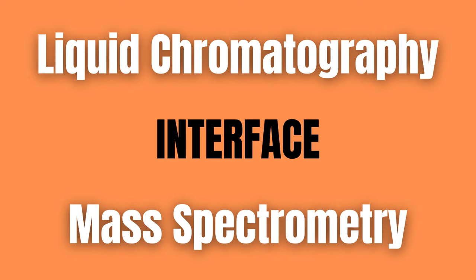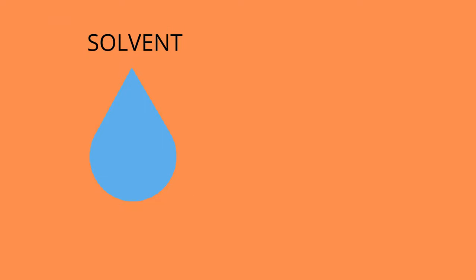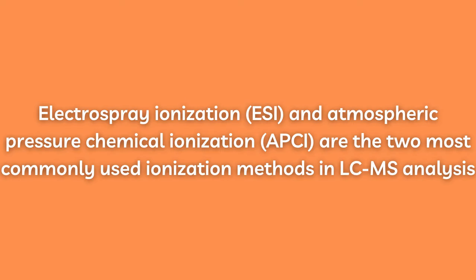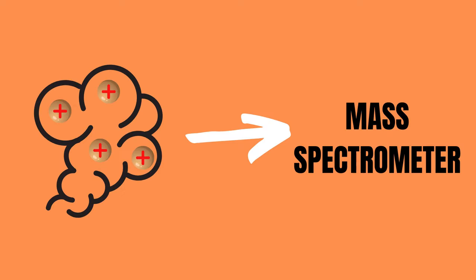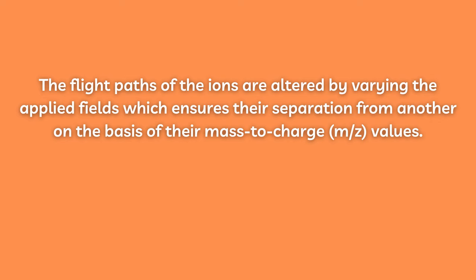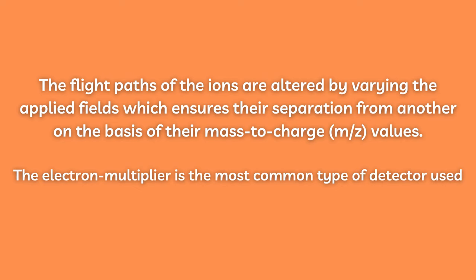The LC and the MS are coupled through an interface. The solvent is evaporated through the application of heat and analyte molecules are vaporized and ionized. This is crucial because the MS can only measure gas phase ions. Electrospray ionization ESI and atmospheric pressure chemical ionization APCI are the two most commonly used ionization methods in LC-MS analysis. Then the analyte ions are drawn into the mass spectrometer where they are subjected to electric fields and or magnetic fields. The flight paths of the ions are altered by varying the applied fields, which ensures their separation on the basis of their mass to charge, or m/z, values. Post separation, the ions can be collected and detected by a variety of mass detectors, the most common one being the electron multiplier.